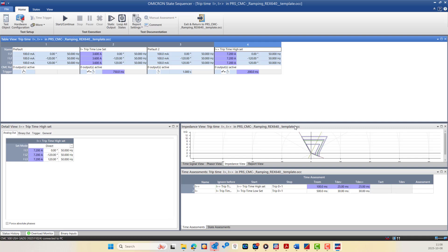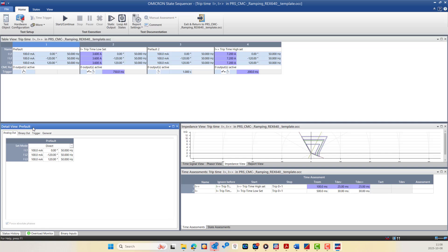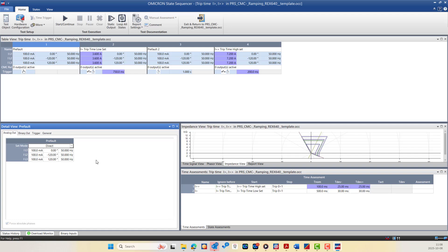The module provides key views to help you configure and analyze each state. The Table View gives an overview of all defined states showing their output values and allowing you to name or rename each state. The Detail View is used to configure each state in depth through multiple tabs. The Analog Output tab lets you set voltage and current values either directly or through calculated parameters such as symmetrical components or fault impedance to ensure a realistic fault simulation.